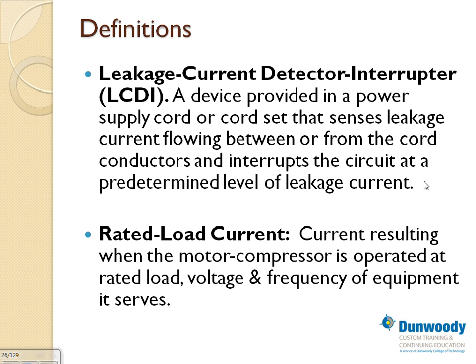With this equipment, guys, they have something called a leakage current detection interrupter device, provided in the power supply cord or plug set, that senses leakage to the ground and trips if there is leakage to the ground in the system. Rated load current: we have a motor compressor operated at rated load. This is the current that you get if you give the motor the rated load, the voltage and the frequency it's supposed to work on. You get something called rated load amps.